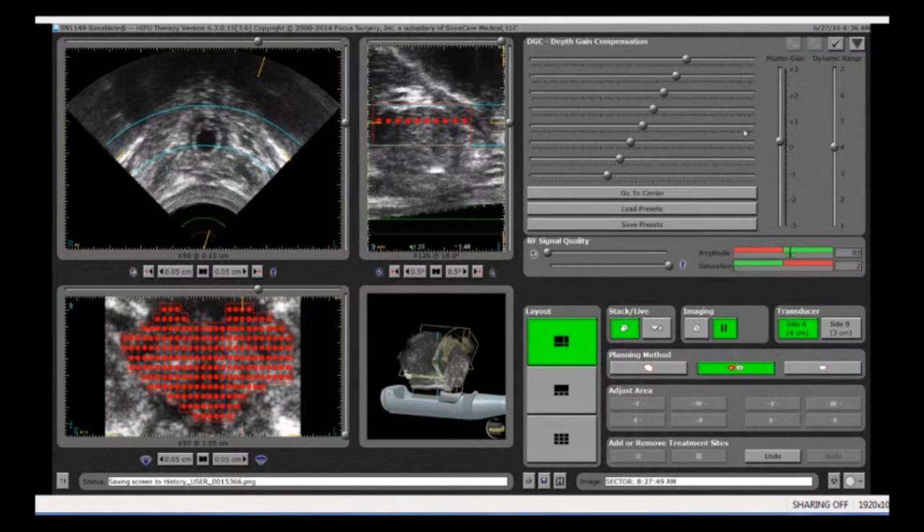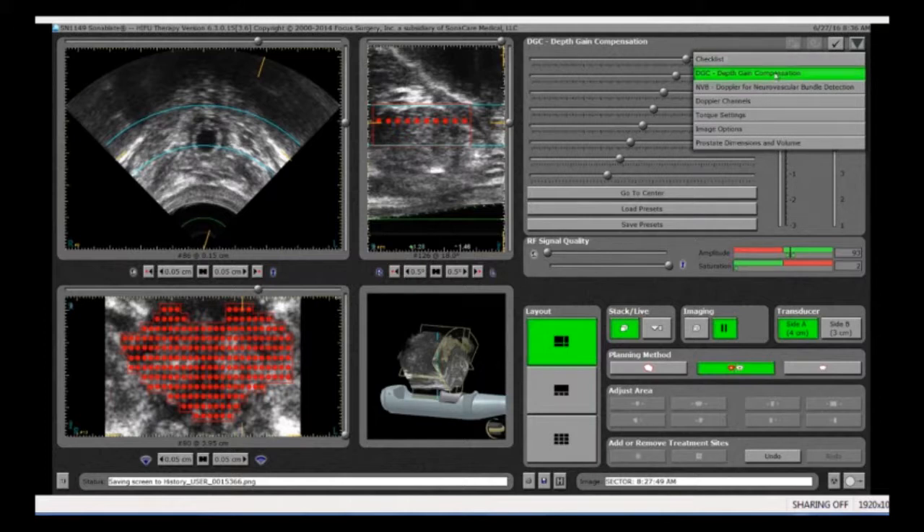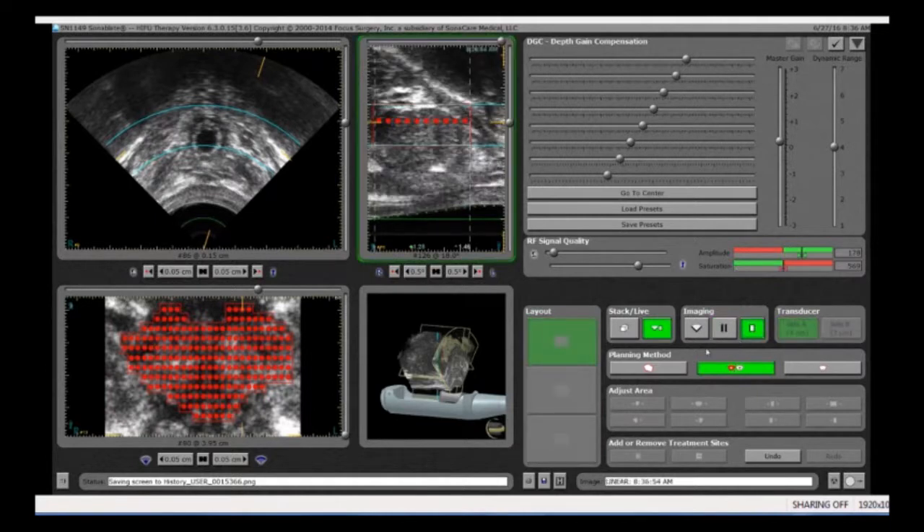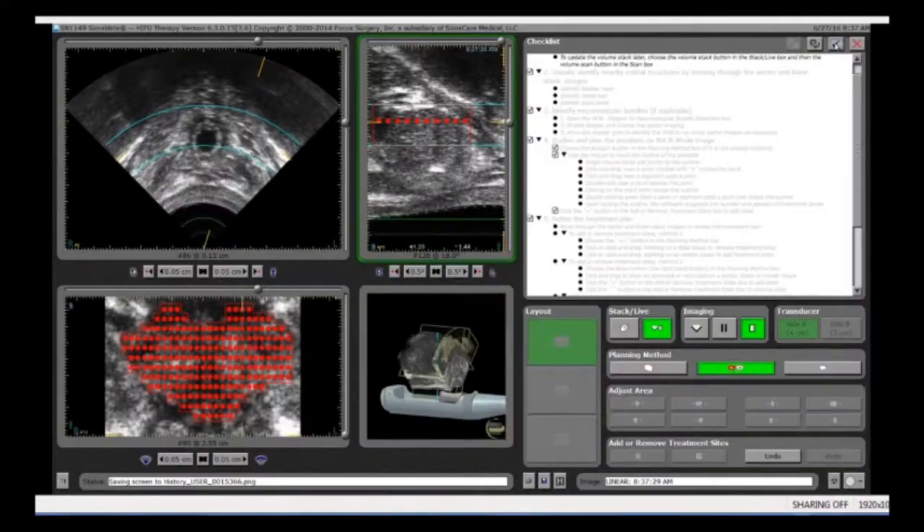Now we're going to do something really important: setting up tissue change monitoring. This is something that's exclusive to the Sonablate system. What it allows us to do is assess how much heat we get in any one area during the treatment. We bring these gates in to line up those areas, and now we're going to see what the signal strength is. We want it roughly around 200 — it's at 182 right now, so I'm going to bring it up just a little bit. This looks like we're ready to go.